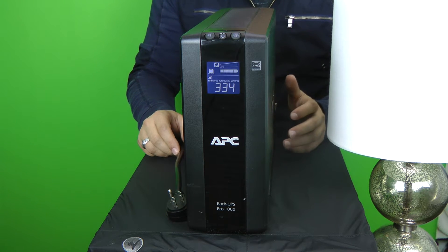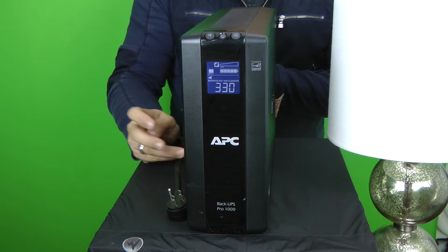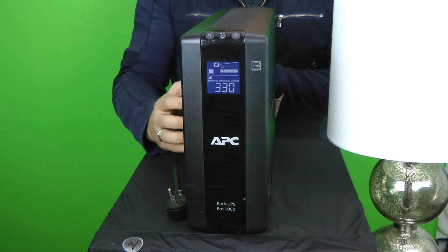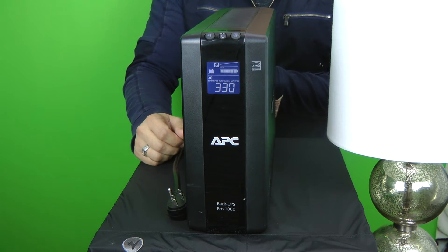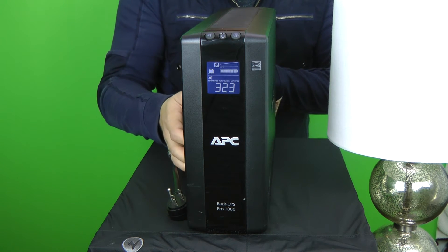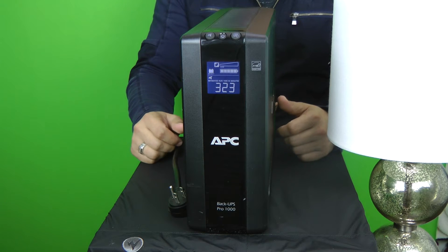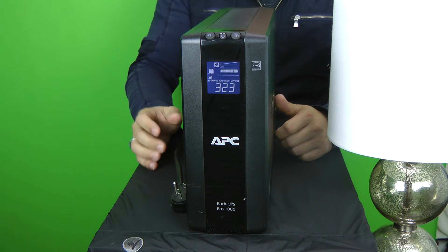What I had to do with this particular device is go to the company that had this one installed. They had two new ones, and I looked at them — sure enough, those two were beeping, signifying something's wrong with the batteries. But the people there just didn't follow through and ask themselves a simple question: why is this thing beeping? I don't know how far APC or these battery manufacturers can go in terms of letting the user know — maybe it should just say 'no battery' or something like that.